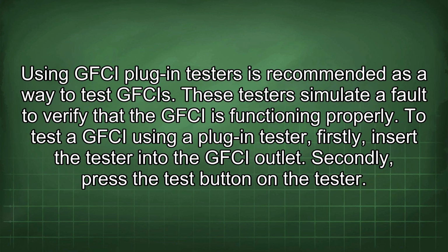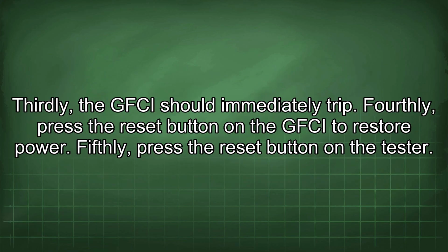Using GFCI plug-in testers is recommended as a way to test GFCIs. These testers simulate a fault to verify that the GFCI is functioning properly. To test a GFCI using a plug-in tester, firstly, insert the tester into the GFCI outlet. Secondly, press the test button on the tester. Thirdly, the GFCI should immediately trip.